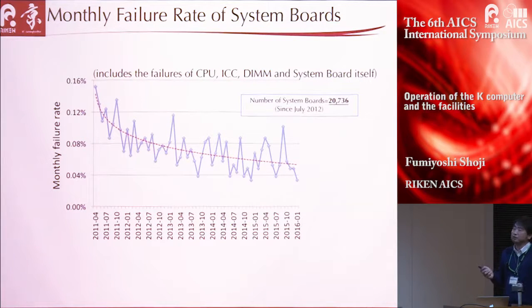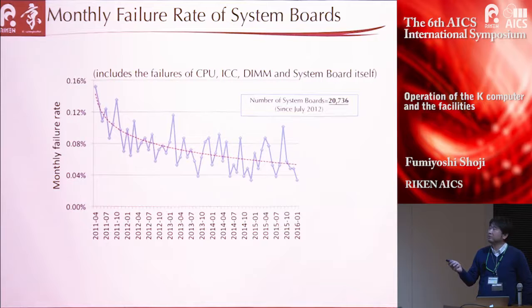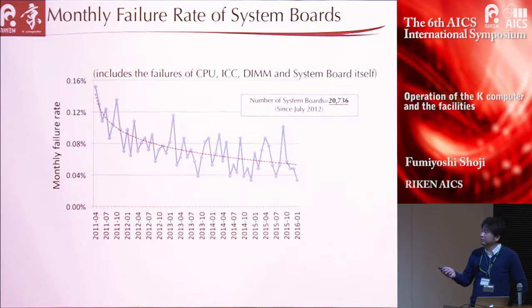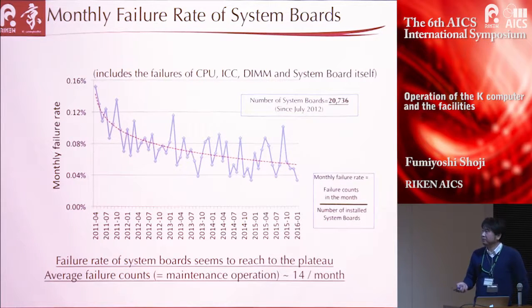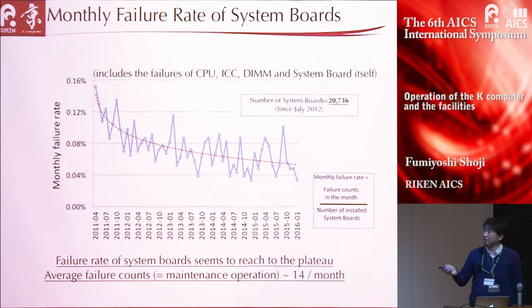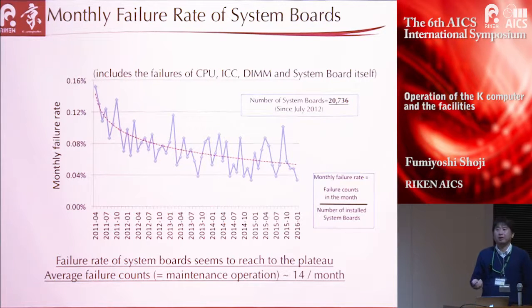The last component is the system board. As I said, system board failures include failures of CPU, ICC, DIMM, and the system board itself. This corresponds to the frequency of maintenance operations. The failure rate of the system board seems to have reached a plateau. Average failure counts, which correspond to the frequency of maintenance operations, were about 14 times per month—in other words, maintenance operations are done on average every two days.